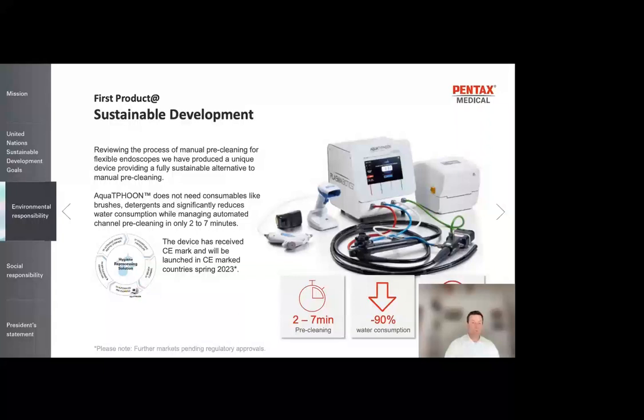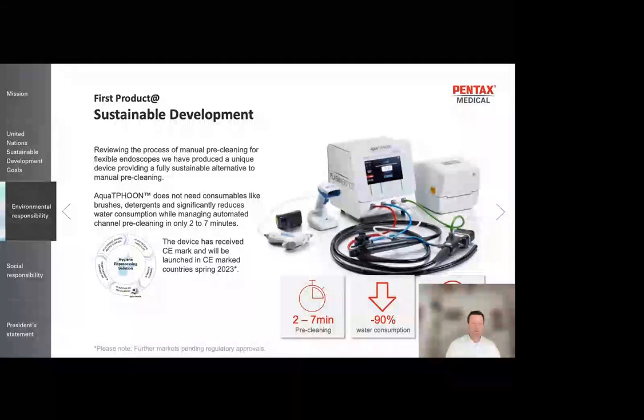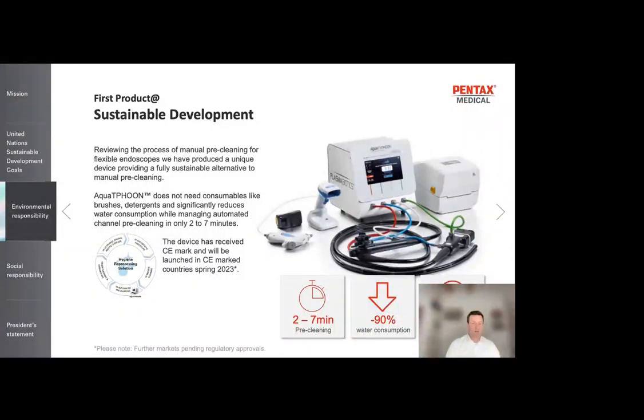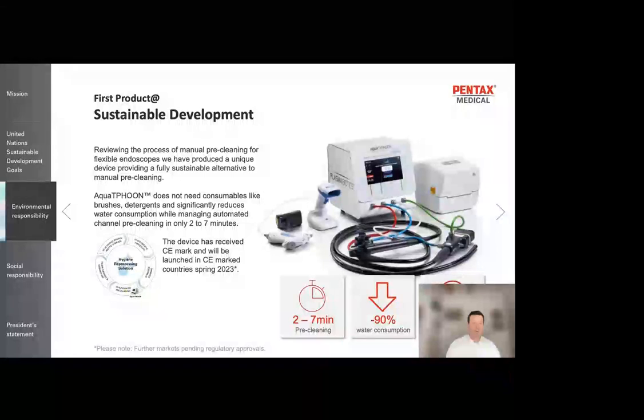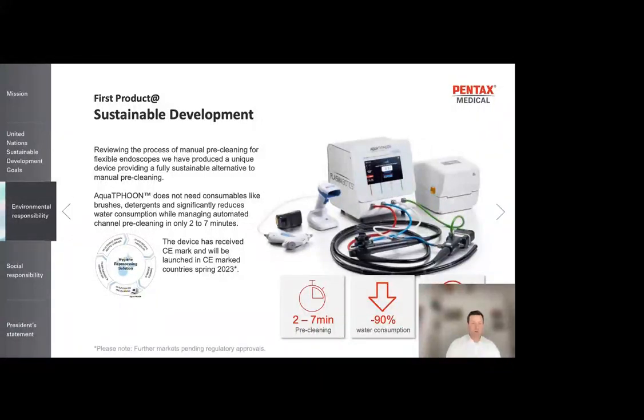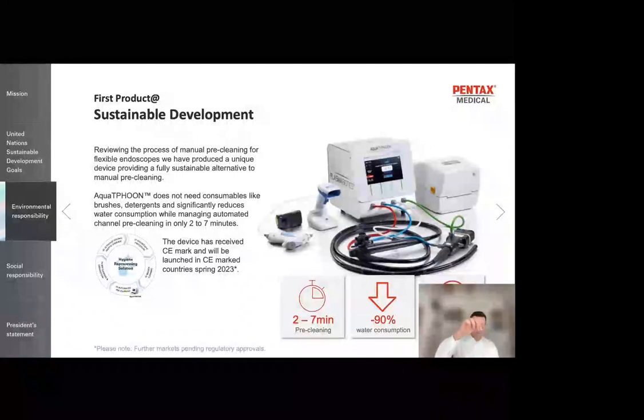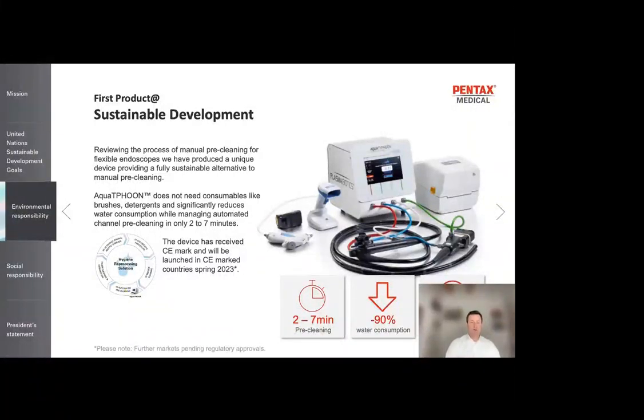Now, let me introduce to you the Aqua Typhoon. What is Aqua Typhoon? It is a new device that will enable us to significantly change our processes of today, because it provides a process that replaces the manual pre-cleaning of flexible endoscopes with a fully automated process, completely sustainable. You all know that when you pre-clean endoscopes, you have to take brushes in order to clean the channels. You need a lot of water, you need a lot of detergent. We need to provide a whole process that typically takes 20 minutes for the pre-cleaning before these endoscopes move into the washing and disinfection machine.